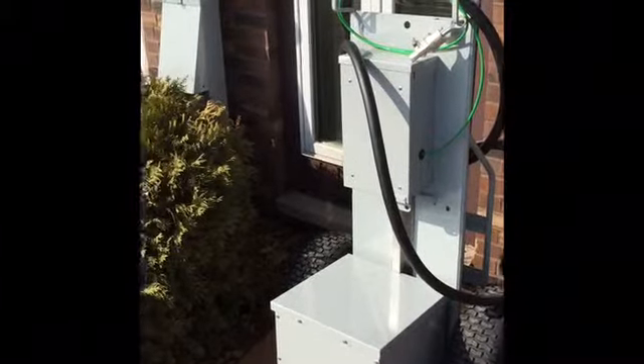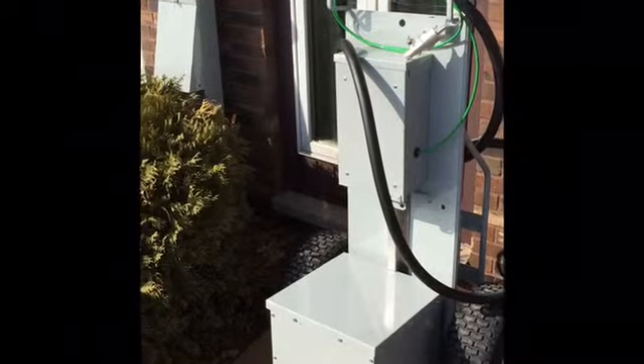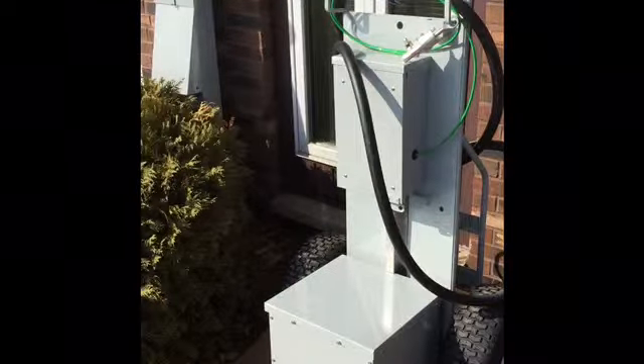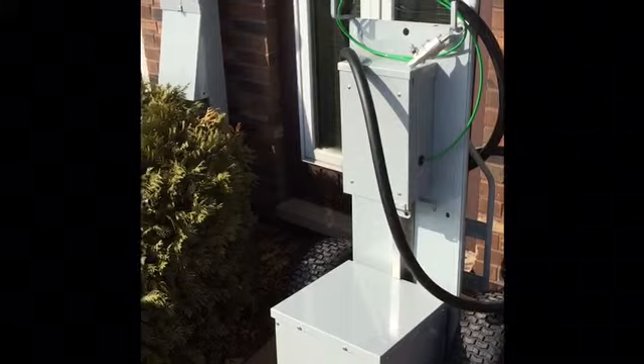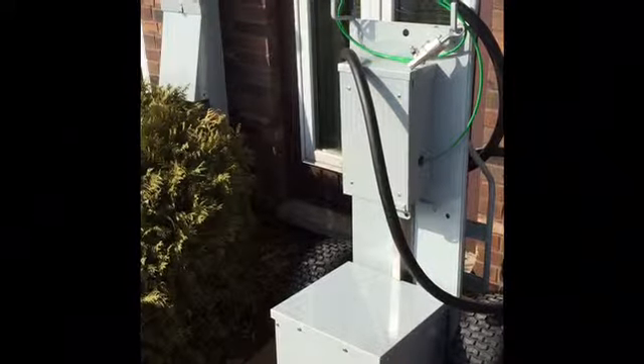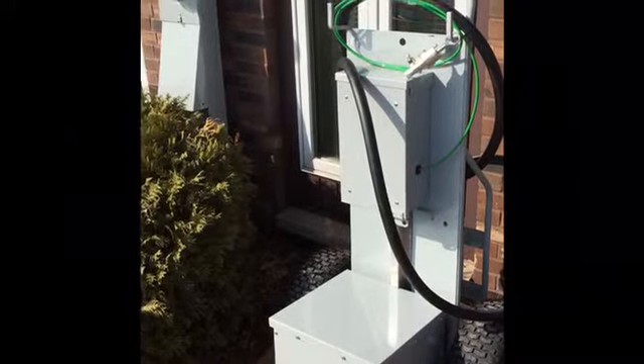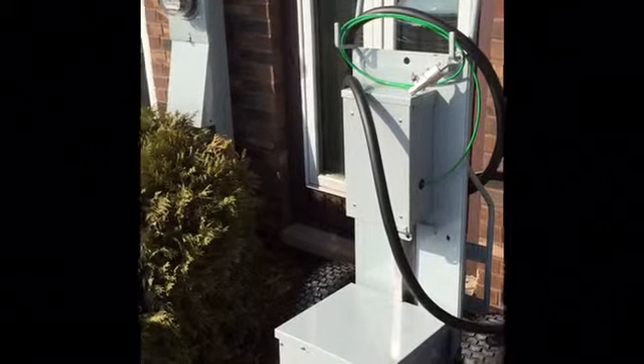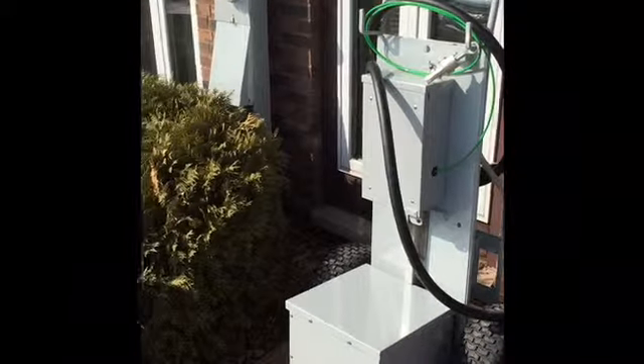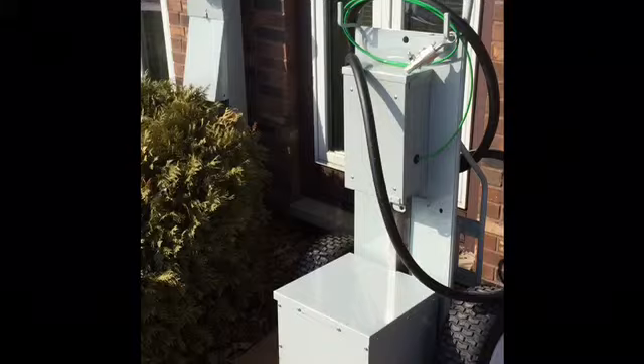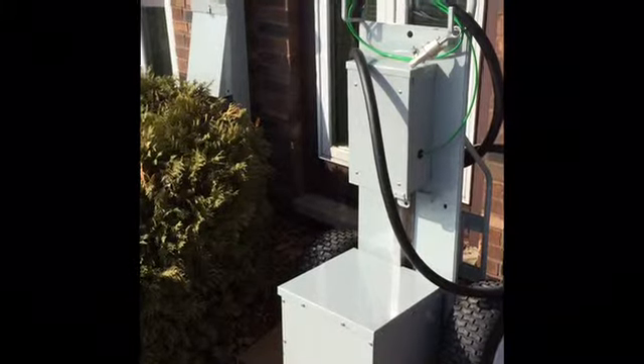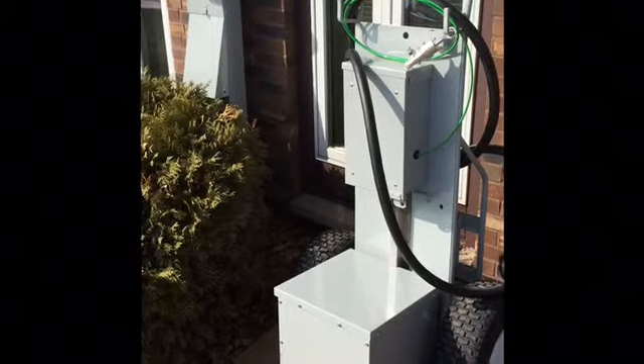And the auto transformer basically can take 120 volts and convert it into 120/240. Again, as long as you have one good 120 volt leg and a neutral, or two 120 volt legs and an open neutral, you can reestablish single phase 120/240 volt service for your customer.